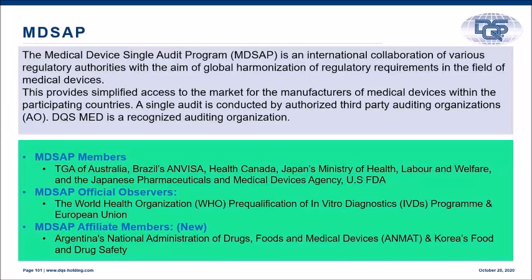So MDSAP, medical device single audit program, is an international collaboration with various regulatory authorities. The MDSAP members are Australia, Canada, Brazil, Japan, and US. These 5 are members, and there are new affiliate members who have joined pretty recently: Argentina and Korea.